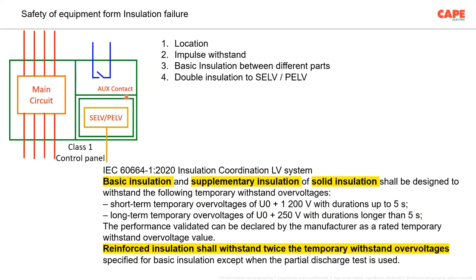Now, you have something working with SELV, let's say 48 volt DC. You have to have basic or supplementary insulation. The performance validated can be declared by the manufacturer as a rated temporary withstand overvoltage value. The manufacturer, while designing the panel board, has to consider these points and declare the performance of these values. Reinforced insulation shall withstand twice the temporary withstand voltage specified for basic insulation, except when a partial discharge test is used.